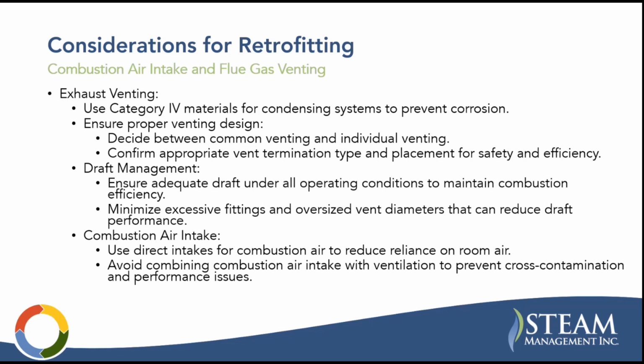On exhaust venting, this is a consideration with condensing boilers. You have to use Category 4 materials to prevent corrosion. You can't just pipe up to your existing flue gas system. Generally speaking, you often are going to run a new flue gas line. So is there space to do that? Is there access to the outside at an appropriate venting location to get those new flue gas lines? It's something you have to look at on every installation. And it can be a challenge, again, with small boiler rooms being in the basement, sometimes in the middle of the building, that type of thing.